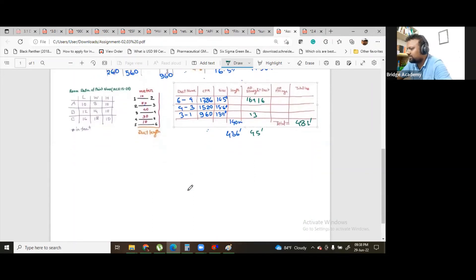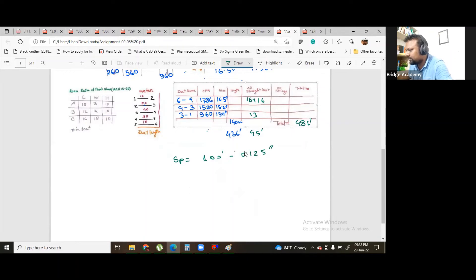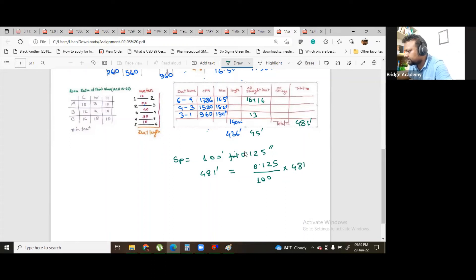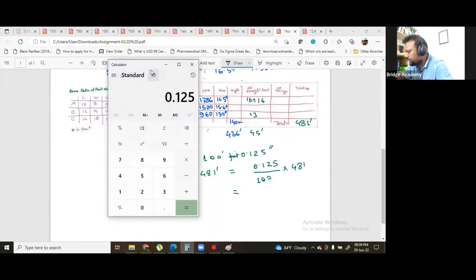This is the ESP — the static pressure. 100 feet. 0.125 inches per 100 feet, 0.125 divided by 100, multiply with 481. The result is 0.6 inch.